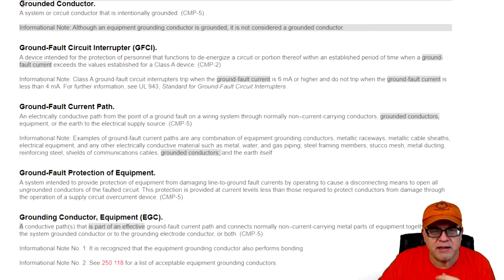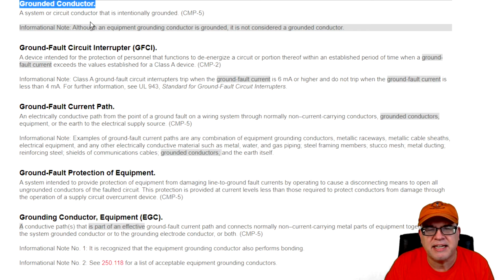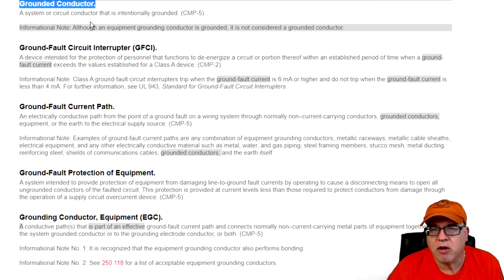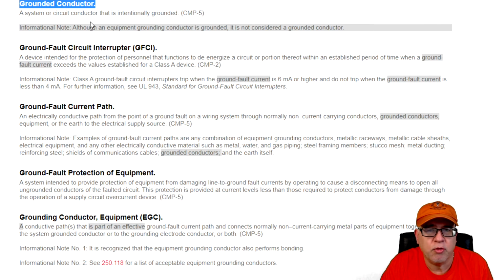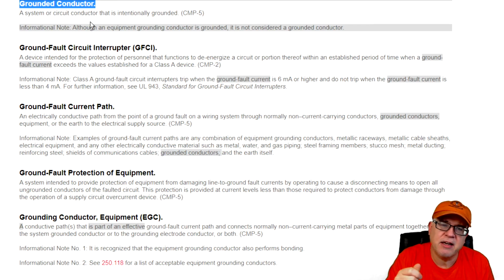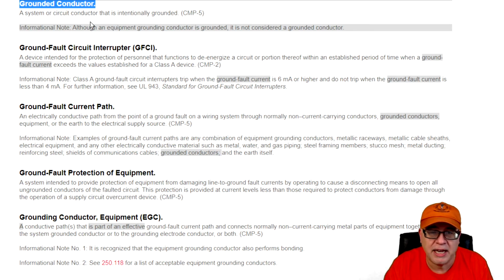The grounded conductor. Very important to understand the terminology. It's a system or circuit conductor that is intentionally grounded. So we talked about a transformer. In a transformer, if I have an XO, which is our grounded conductor, it is connected over with a system bonding jumper to the frame, and relative to the XO it's also connected all the way to the electrodes, which are in the earth. Then that is a grounded conductor.